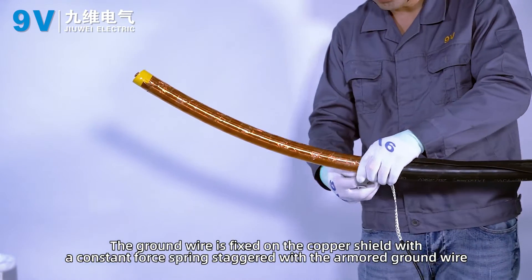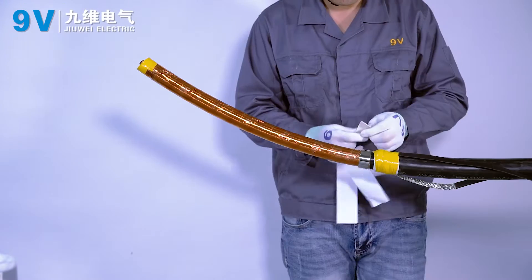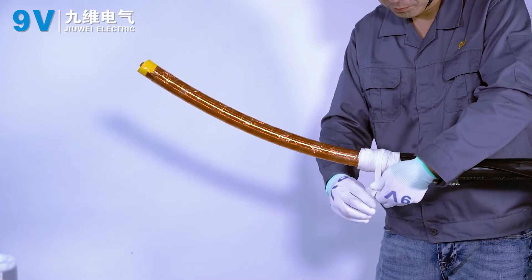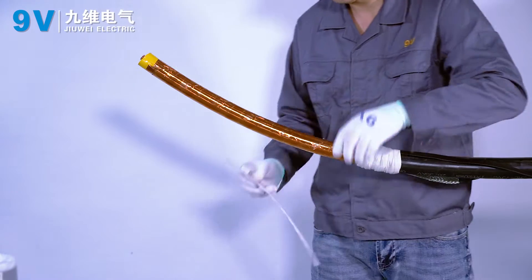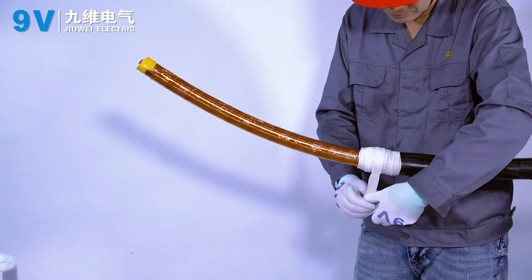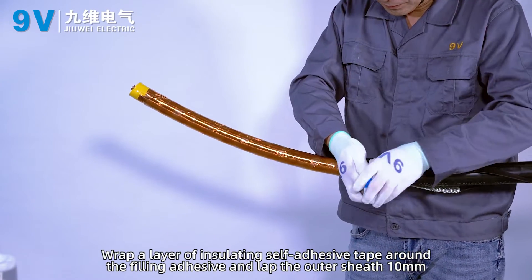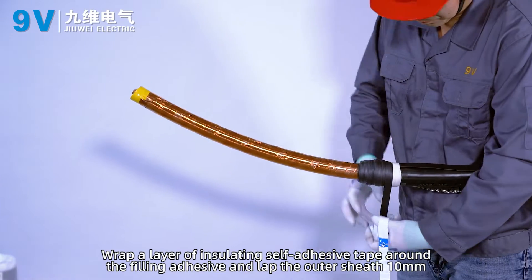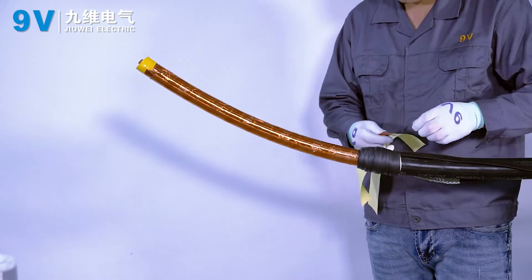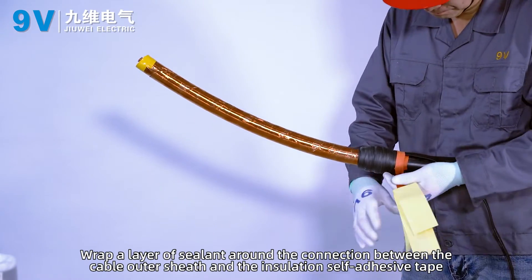The ground wire is fixed on the copper shield with the constant force spring, staggered with the armoured ground wire, and the filling glue is wrapped from the constant force spring to the outer sheath. Wrap a layer of insulating self-adhesive tape around the filling adhesive, lapping the outer sheath 10 mm. Wrap a layer of sealant around the connection between the cable outer sheath and the insulation self-adhesive tape.